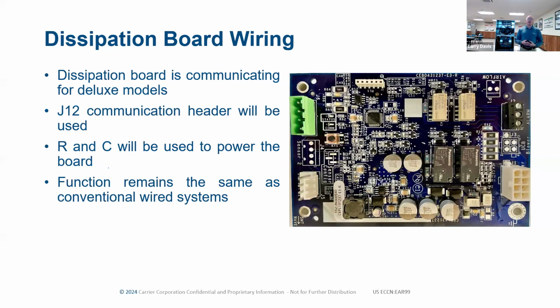Now, the reason for that is we're sending power to the dissipation board before it goes into the furnace control. If that fuse blows on the furnace control and it shuts power down to the furnace, our dissipation board's still going to be powered up. So it just kind of gets to the priority level, if you will. But yeah, you'll still wire R and C to the dissipation board.